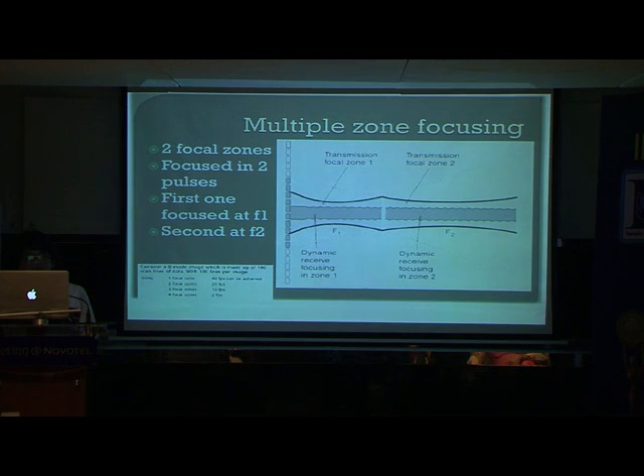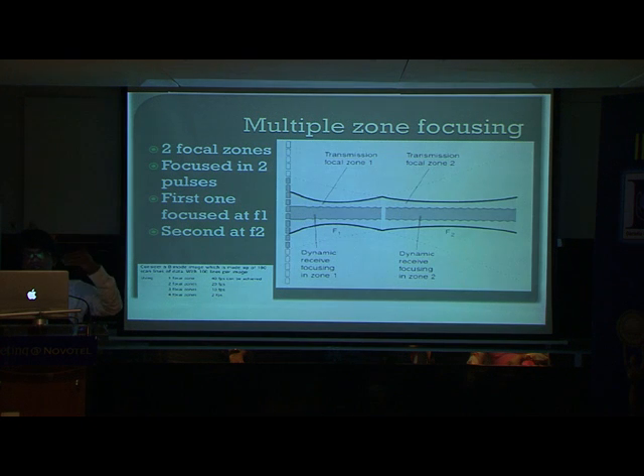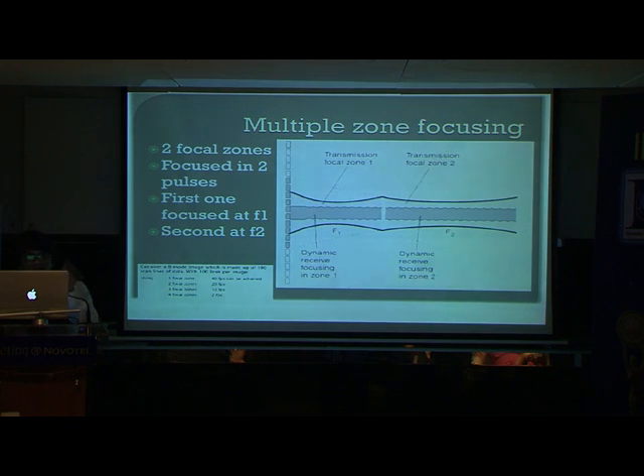Some machines offer multiple focusing zones, which is important when you have a target area in one focal zone and another important structure in another. For example, during a brachial plexus block, the deeper focal zone contains the subclavian vessels and the near focal zone is the brachial plexus. To ensure the needle is not transgressing the brachial plexus and going into the subclavian vessels or lungs, you must adjust the dual focus zone. These are important factors for optimizing image quality.